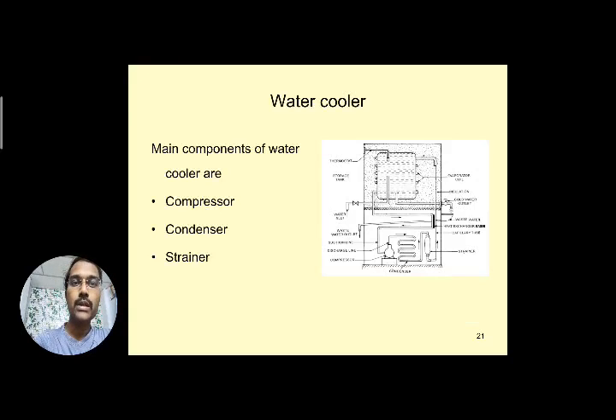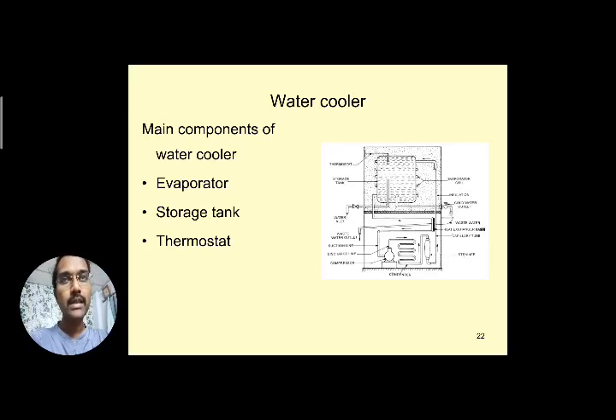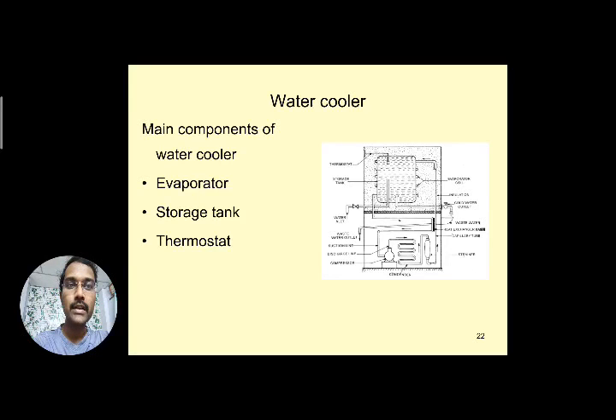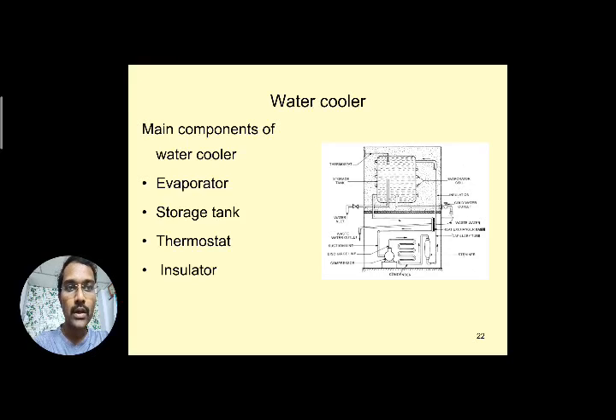The main components of the water cooler are: compressor, condenser, strainer, expansion device (capillary tube), evaporator storage tank, and thermostat. The thermostat is a temperature control sensor — you can adjust it to maintain the required temperature, such as 10 or 15 degrees centigrade. Insulation such as glass wool or thermocol is provided around the tank to prevent heat exchange from the surroundings.